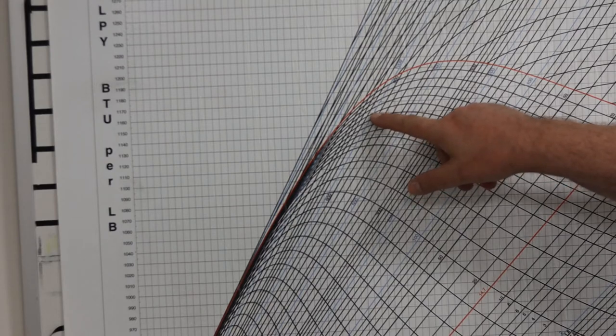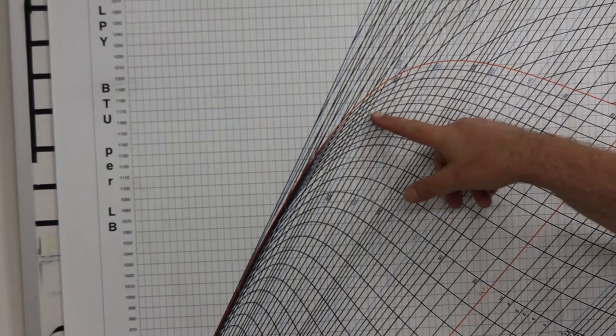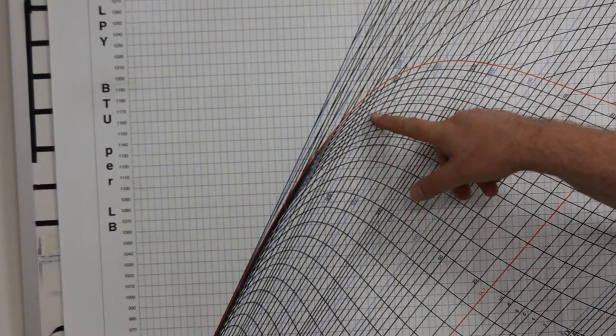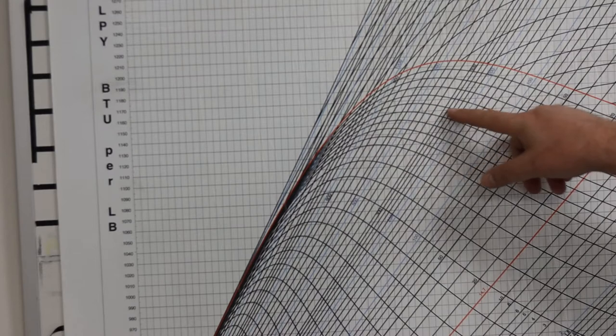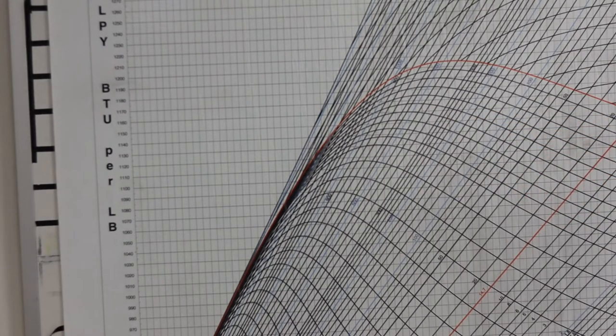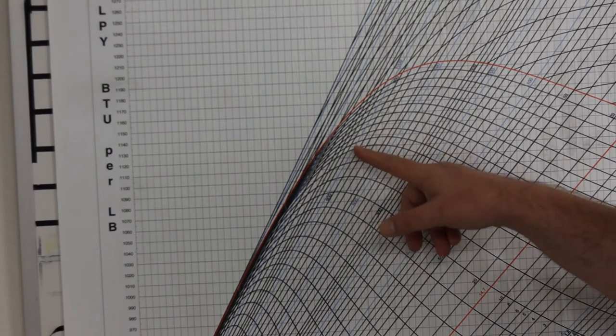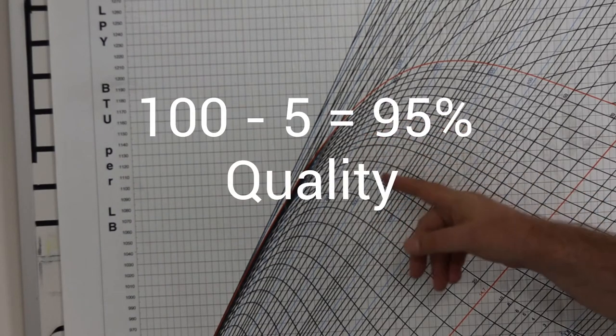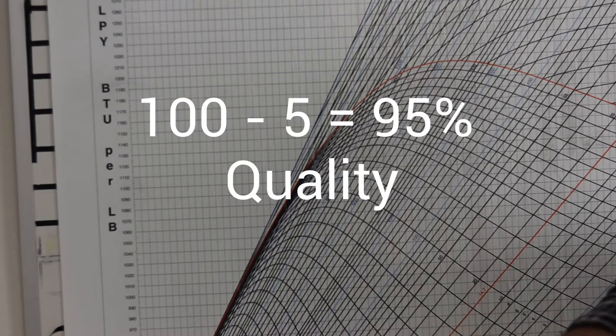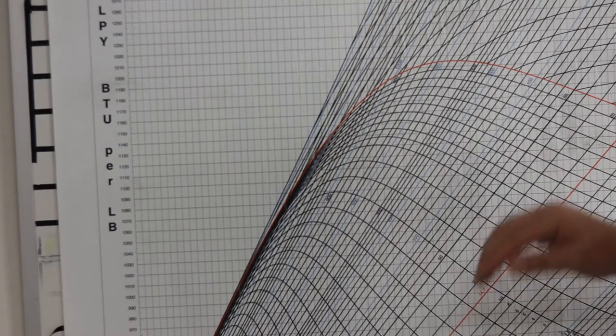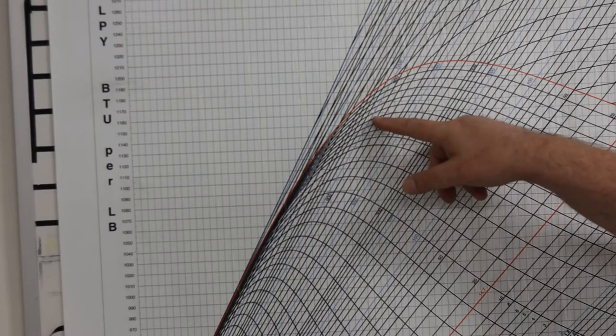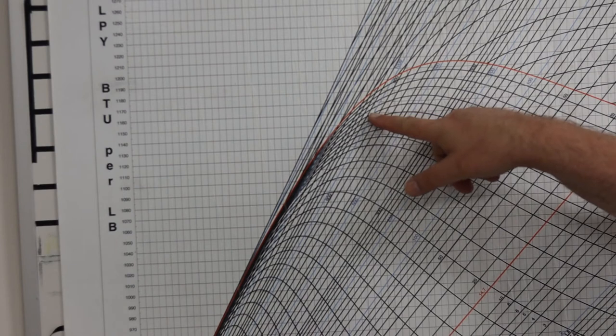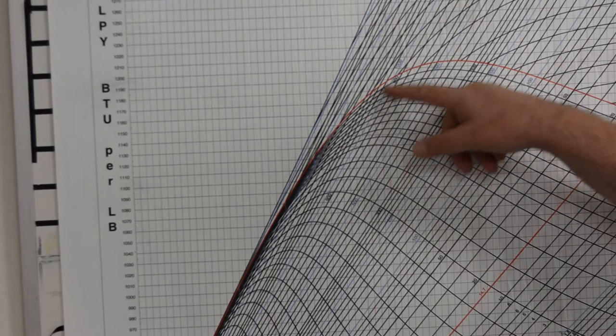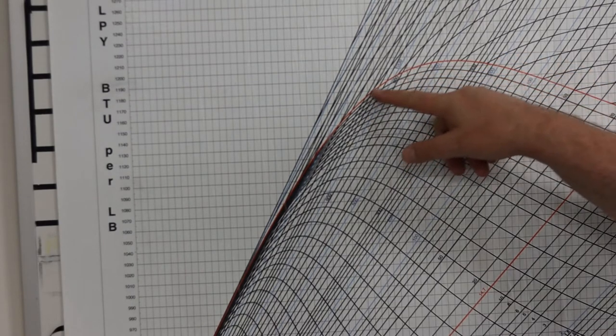Well, that tells me I'm below the red curve, so I know it's a saturated steam water mixture. And then I can follow that constant moisture line, and that's 5. So 5% constant moisture, which is 95% quality. So it's 95% steam at that point. 95% quality is 95% steam. That's a nice way of thinking about it. And I'm really close to being dry saturated steam.